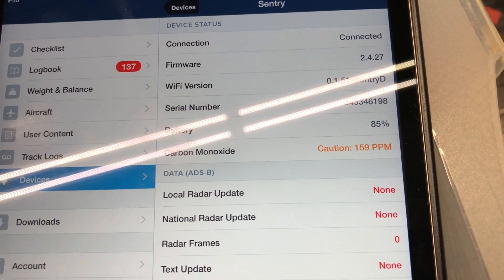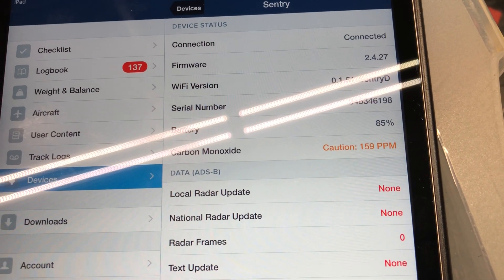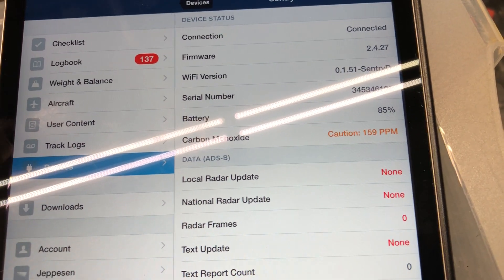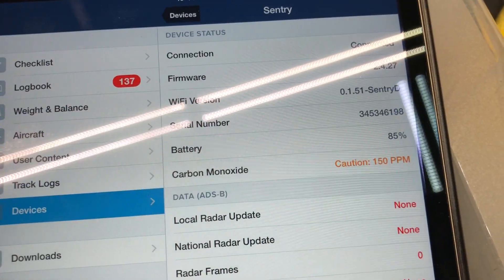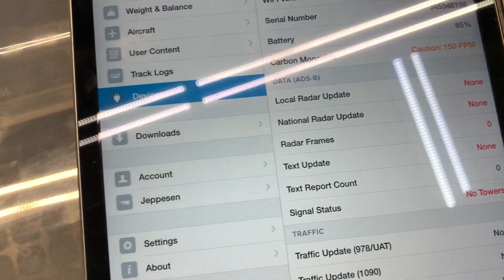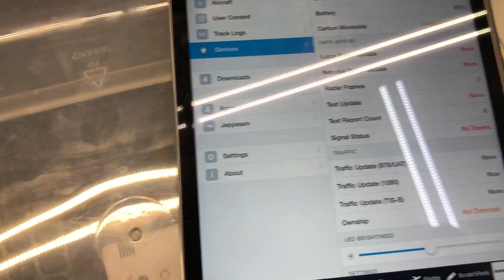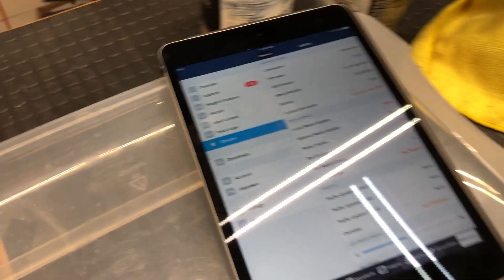154 parts per million. 159. So it's still reading the carbon monoxide that I have pumped into this little chamber here. 156. Now what I want to do is I want to get it up to a level where we get the audio alert from the piezo buzzer on the system.